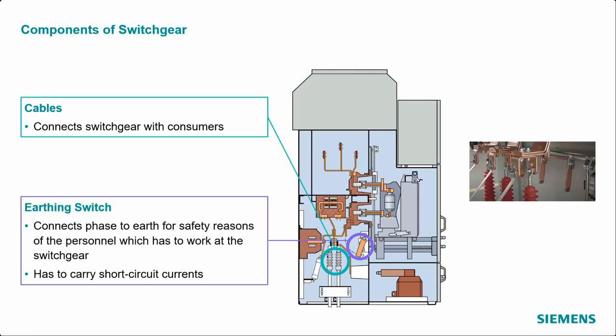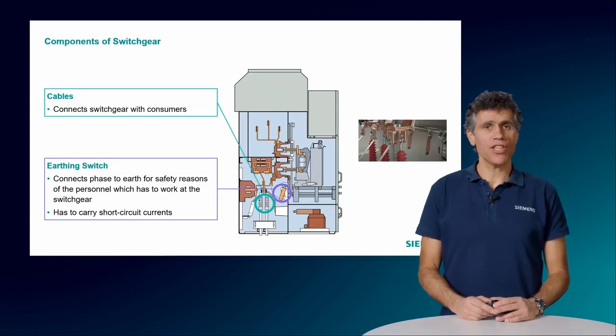And now we come to the final destination of the electrical power after the switchgear, the cables. The cables carry the power and connect the switchgear to the consuming device, which can be a motor, a transformer, a line, a capacitor, etc. Cables are not part of the switchgear and are usually mounted on site. On the way to the cables, an earthing switch might be placed. If energy is flowing, this must be open at all times.